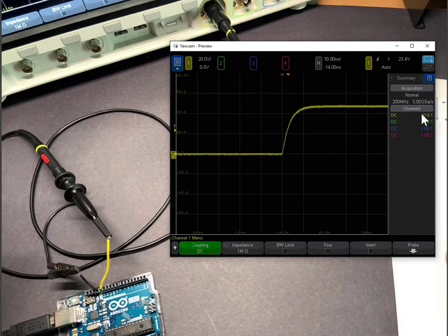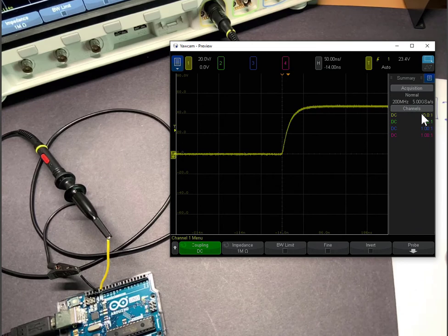And that's why you want to be really careful using the 1X probe. Remember, it's got that series 260 ohm resistor in the cable itself. If you want the highest bandwidth for the probe, you always want to use the 10X setting. If you use the 1X setting, just remember you have an artifact you have introduced. Yes, with a 1X setting we're not attenuating the signal, but on the other hand, we also are limiting the rise time that we can see.